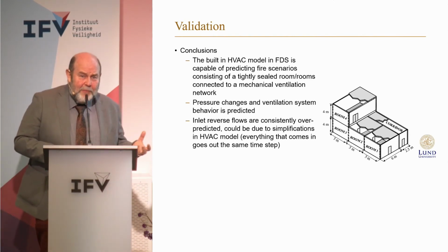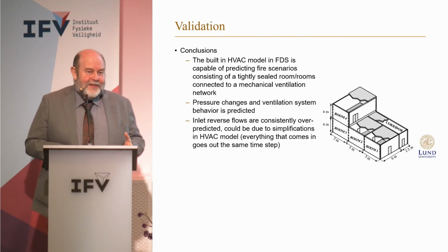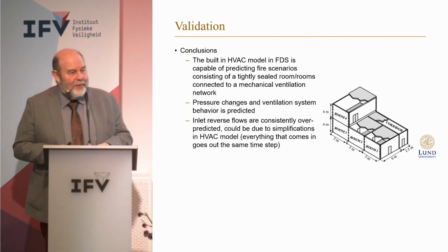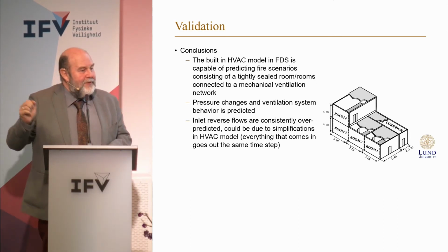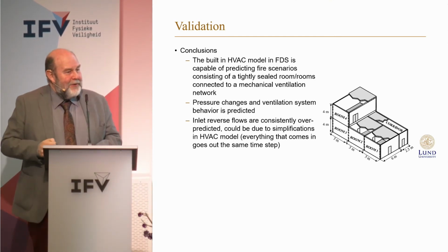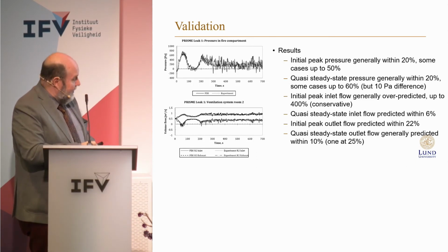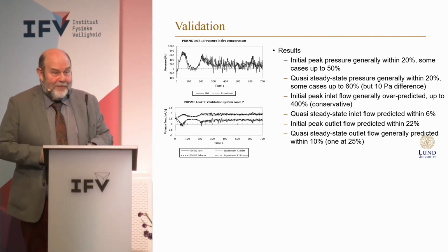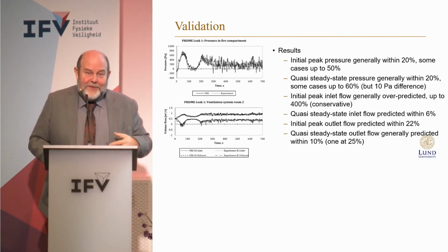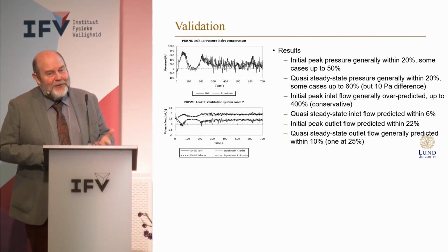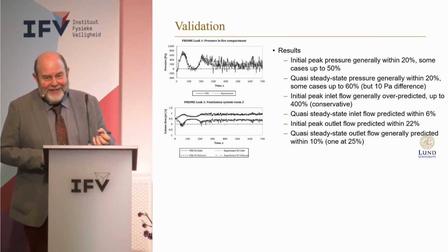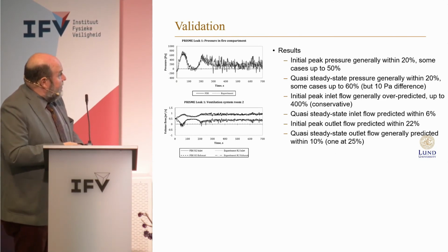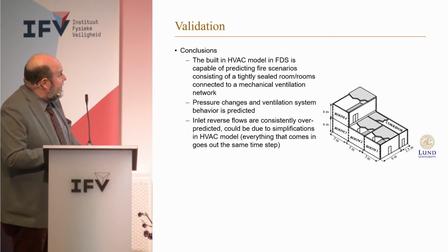of this PRISME project, we all did simulations where, and I'm a little bit ashamed that one of the simulations I did myself, you put the boundary condition of the ventilation of the test. So you had this curve, which I showed here, and this was put into the model as a boundary condition. And of course that gives you already much better results, but it's not true, because in reality you will not get that data. You have to predict this behavior. But we managed to get to that.